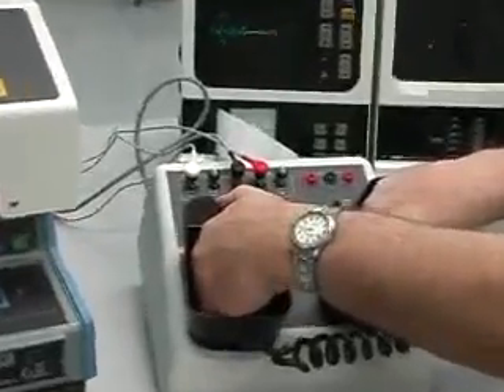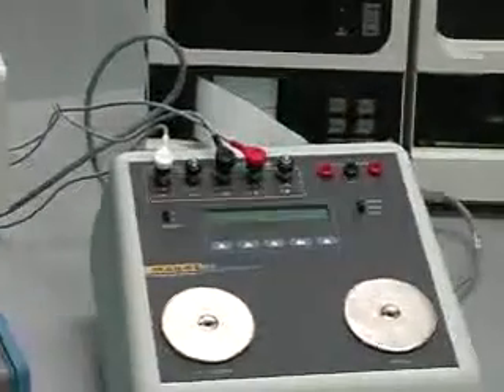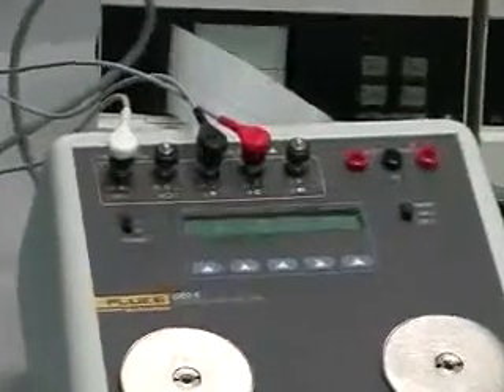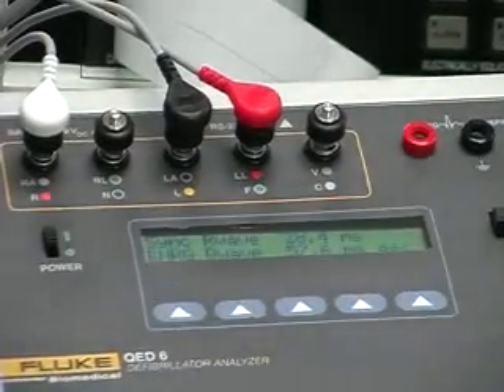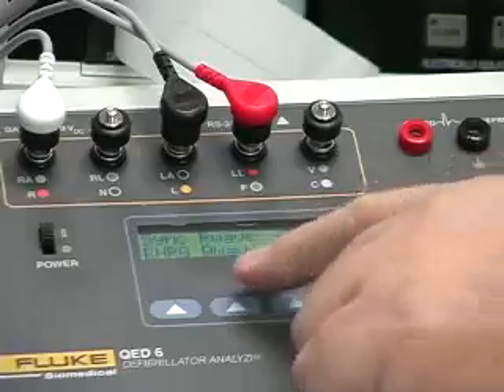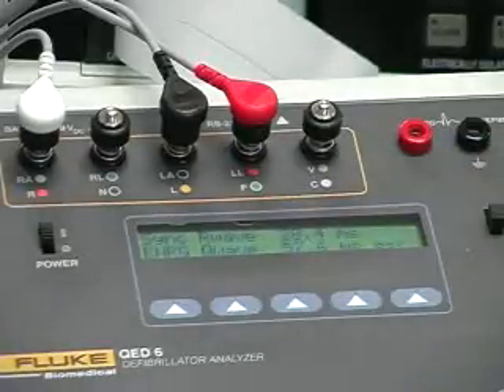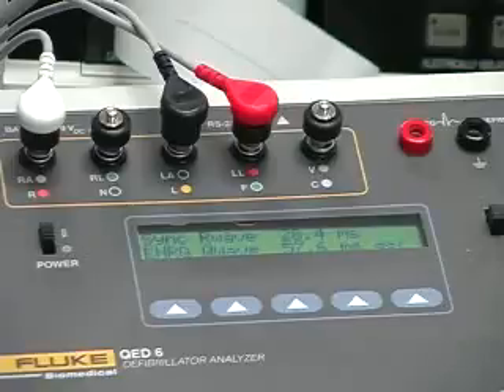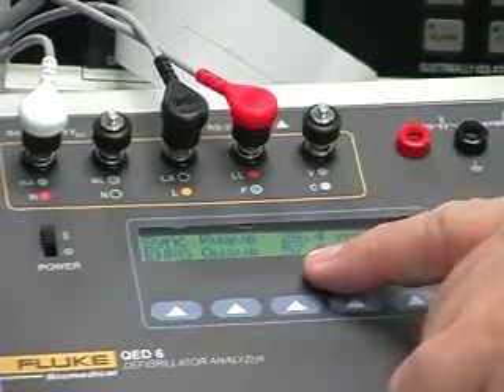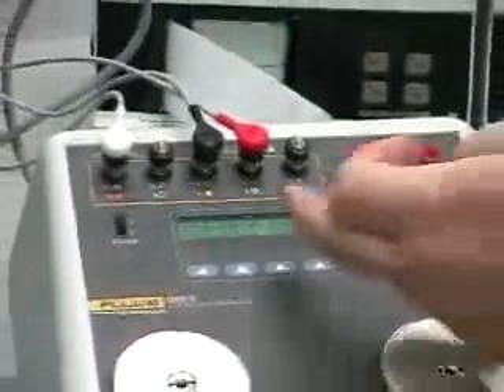Okay, so it discharges, and then the ECG waveform comes back up, and we display the time. The QED6 is a little different from other analyzers in that we display both the time from the Q wave, the initial contraction of the right ventricle, and it also displays the time from the peak of the R wave. So since the Q wave comes first, the time from the Q wave was 57.6, and from the peak of the R wave, it's like 28.4.